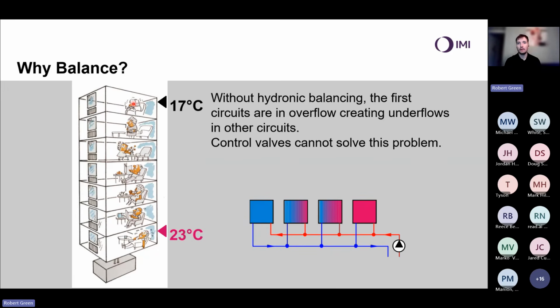And control valves themselves, we're going to look at control valves in a few sessions' time. But fundamentally, control valves do not solve this issue. Yes, a correctly set up control system should be compensating for excessive flow and excessive output from my emitters, but it's going to take some time to do that. And we're going to need to be ensuring we are correctly proportionally balancing this water volume to get the right flow to the areas we need in the system. And in simple terms, in heating, an underflow is going to be too cold. We aren't going to have sufficient heating. And an overflow, we're going to be too warm. And that's going to be vice versa if we're looking at a cooling system. Too much flow in a cooling system, too cool, not enough, too warm.